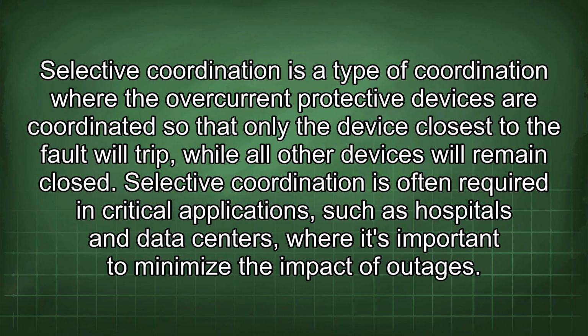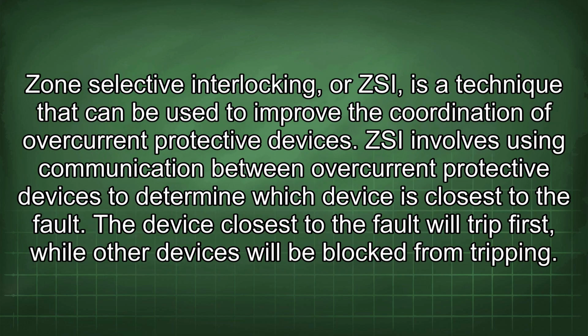Selective coordination is a type of coordination where the overcurrent protective devices are coordinated so that only the device closest to the fault will trip, while all other devices will remain closed. Selective coordination is often required in critical applications such as hospitals and data centers, where it's important to minimize the impact of outages.